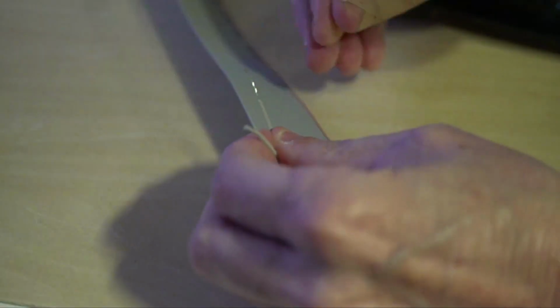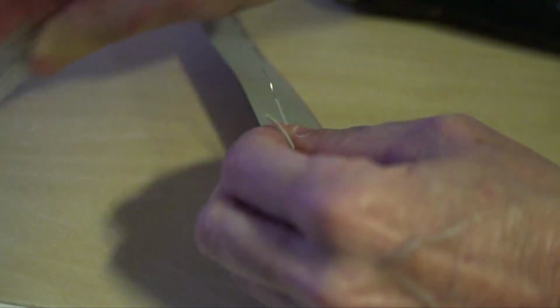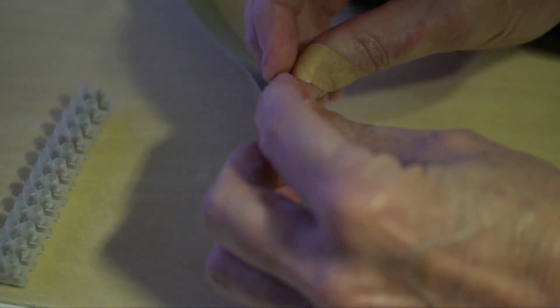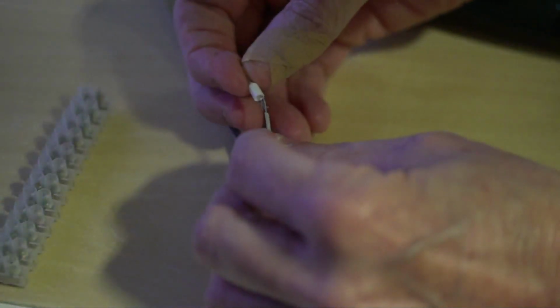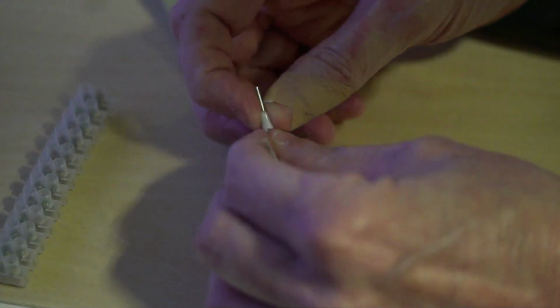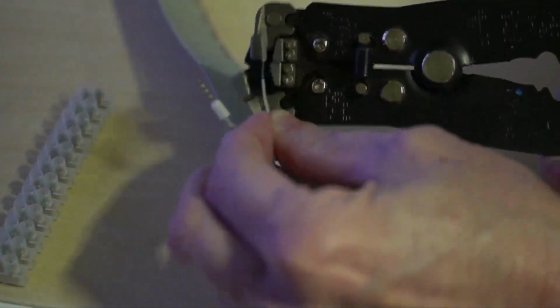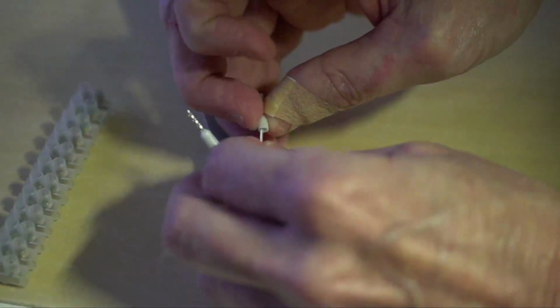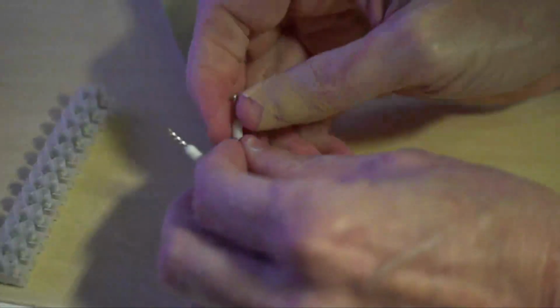I am going to be using a wire ferrule for this because it's going to make the connection better. And putting a wire that's this thin inside of a terminal strip is very difficult. So what I will do is I'm going to fold this in half to double the surface area, so it'll fit with a wire ferrule a little bit better, a little more snugly. And make sure that you tug well on these to make sure that it's a good connection.